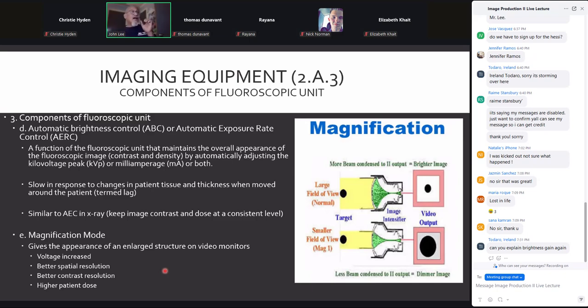Okay, so if we're doing a barium swallow on a patient, or even an upper GI, and we're following in an AP position, we follow the barium down, and then we have the patient oblique or turn lateral. When they do that, the part thickness changes. So the technique that's being utilized is not sufficient, and the ABC would increase the technique so that it would bring the brightness back to where it would be. Now, if you've done any fluoro, you would see this: sometimes the radiologist will stop fluoroing while the patient's making a move and getting into position. That cuts down on the adjustment itself, but when it comes back on, you may see it's going to be really, really dark, and then it'll get brighter very, very quickly. That's the ABC kicking in. Okay.